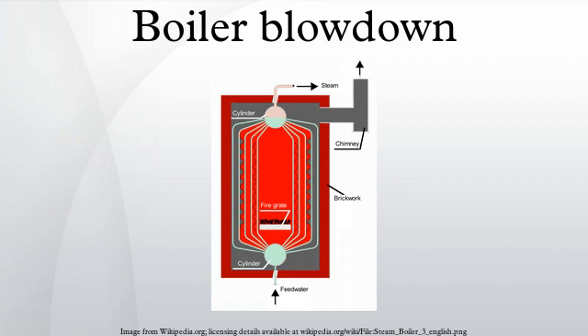There are two types of surface blowdown fittings. The simpler is a pipe entering the steam drum at the normal water level. A more sophisticated skimmer arrangement attaches a swivel joint to the pipe for a short length of pipe suspended by a float. The skimmer may be more effective at removing floating oil which might otherwise cause foaming.